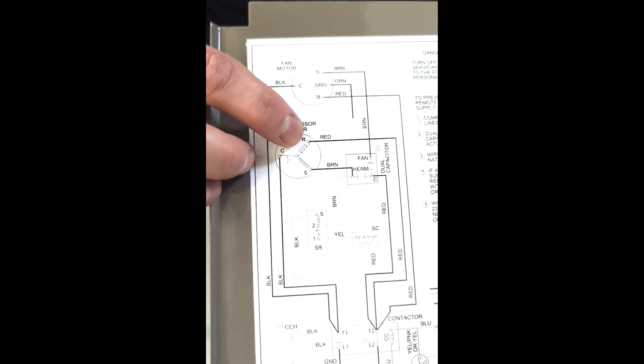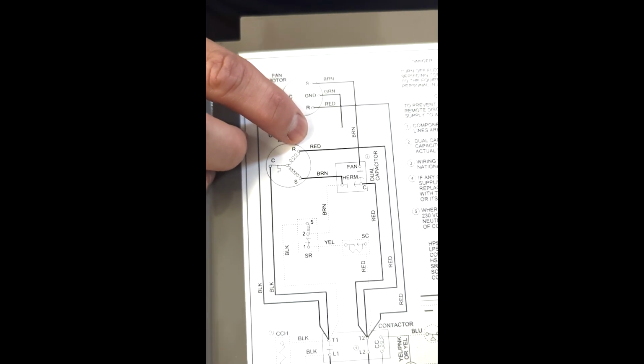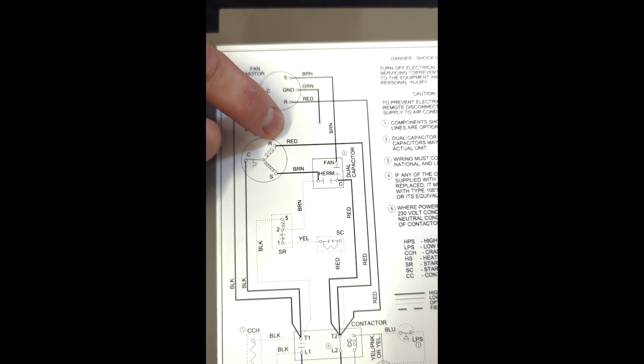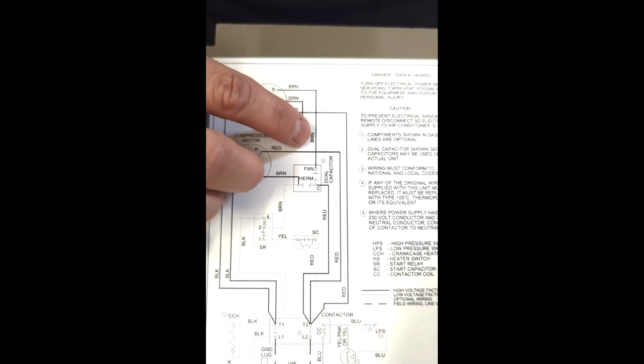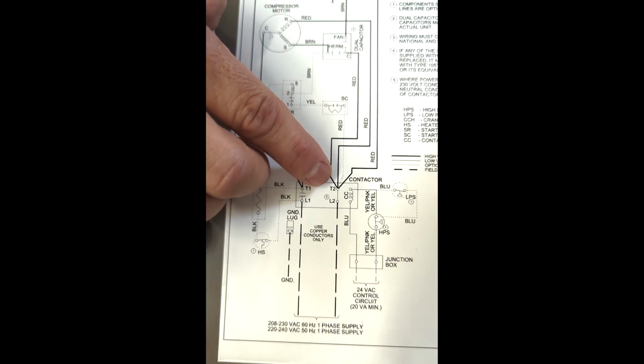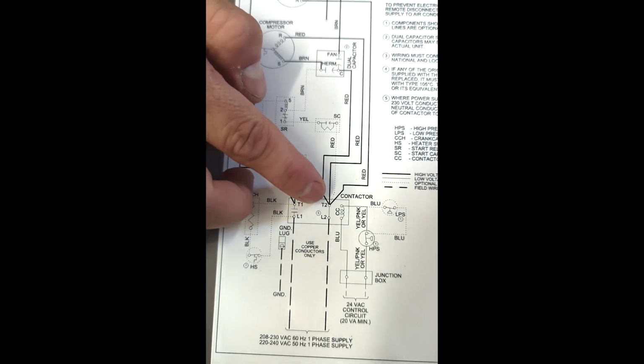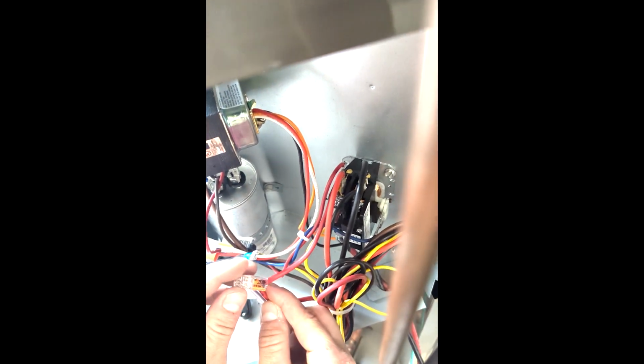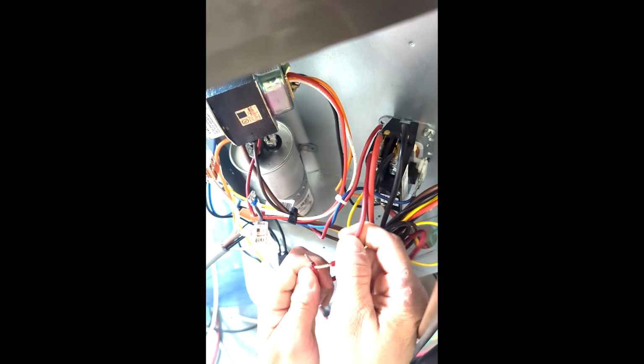Now, once we've done that, we go back to our wiring diagram, and we're going to go to the R wire, okay? This is a red wire on our air conditioner. It could be a different color on yours, but it's red on ours. So this red wire, if you follow it, goes down to T2 on the contactor. Our air conditioner is a little bit different because we use this as a test model. It's already got one of our WAGO connectors on here, but traditionally your R wire is together.